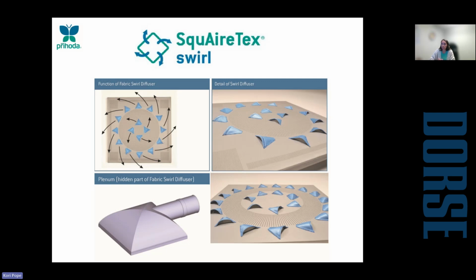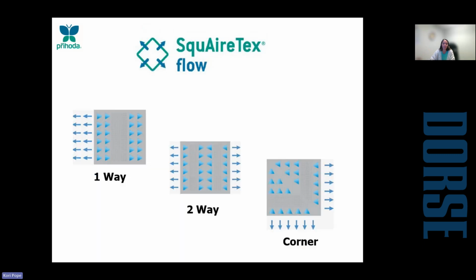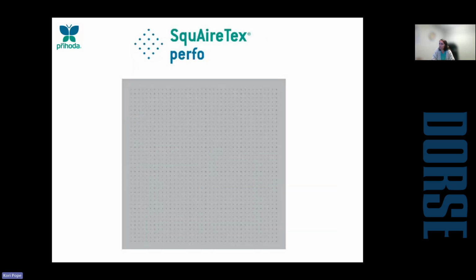The first one that I'm going to talk on is our swirl. So the swirl motion just induces supply air. It provides high volume induction without causing any type of drafts on the occupants. We can also provide what we call the flow. So this just uses pockets and perforations for directional flow depending on the room's requirements. And then the one that we have had the most success with is just our standard perfo face. So this is just simply a perforated face that provides laminar air distribution. So any of our SquAireTex options will be great for any type of labs or kitchens. And because they're completely non-ferrous, they're also great for MRI rooms.